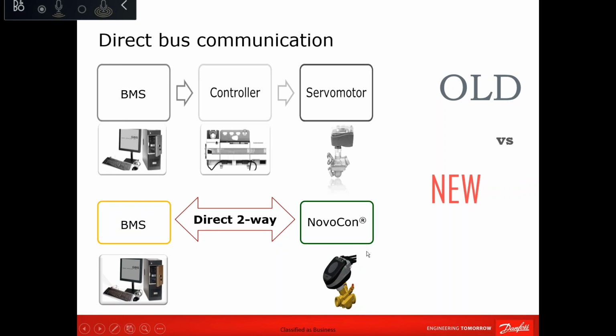Now, in case of Novocon, as we said, it has its own control logic, which means you can use any variable inputs and outputs to control based on the room temperature, based on the return temperature, based on any variable you need. So there is no more need for this controller in case you are using an EC fan motor. An EC fan motor is a motor that will work with 0 to 10 VDC command to change the fan speed. So if you have that in your system, then you only need the Novocon, BMS, and the unit. How you will change the temperature set point, this is an IP accessible address, so you can just change it via your mobile by accessing the IP address of that unit specifically.